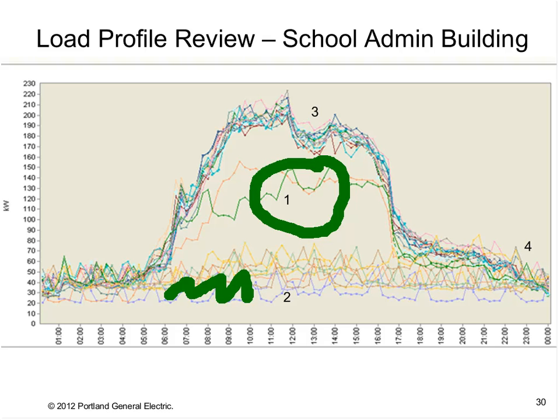Well, we did a high bill check and then found that someone had cranked the heater on in the snack bar up to 90 degrees. So during the summer, the heater was going on and off trying to keep up to 90 degrees. So that didn't help them too much, but that's just one thing you could find. Obviously, like I said, this cycling is definitely something to investigate.